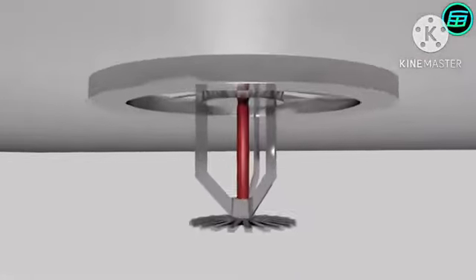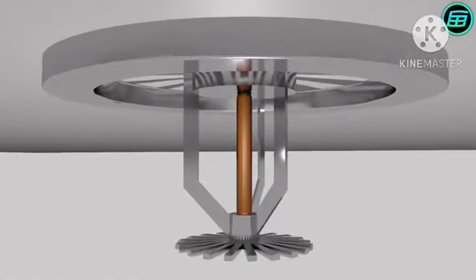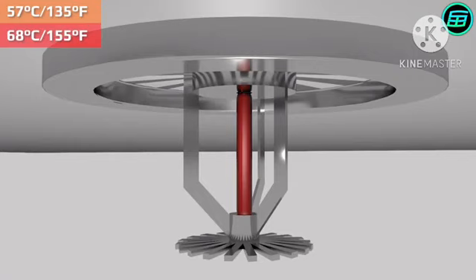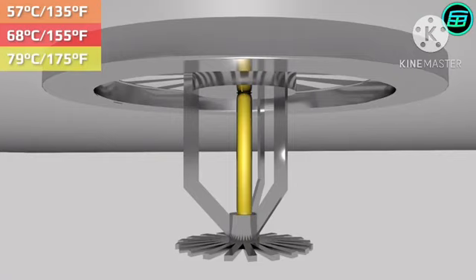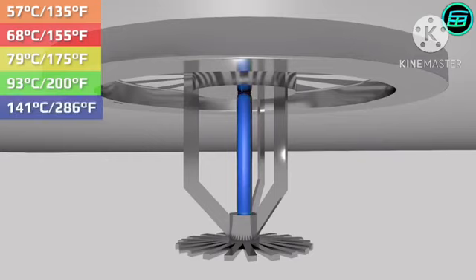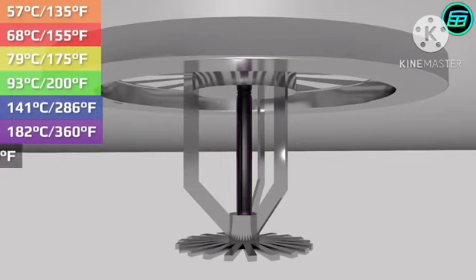There are different types of glass bulb filled with different liquids, and these are color-coded. Orange bulbs have an operational temperature of 57 Celsius or 135 Fahrenheit. Red bulbs 68 Celsius, 155 Fahrenheit. Yellow bulbs 79 Celsius, 175 Fahrenheit. Green bulbs 93 Celsius, 200 Fahrenheit. Blue bulbs 141 Celsius, 286 Fahrenheit. Purple bulbs 182 Celsius, 360 Fahrenheit. And black bulbs 227 Celsius, 440 Fahrenheit.